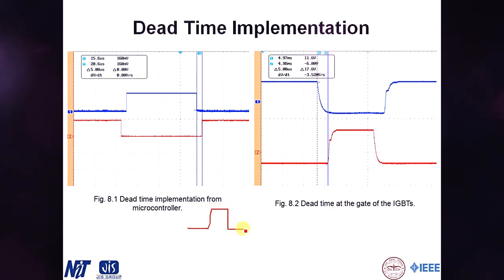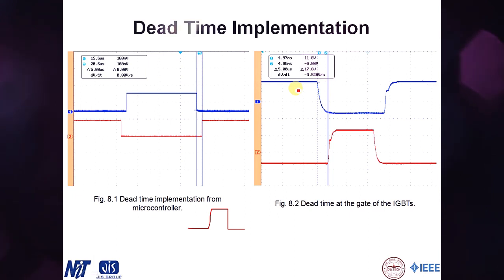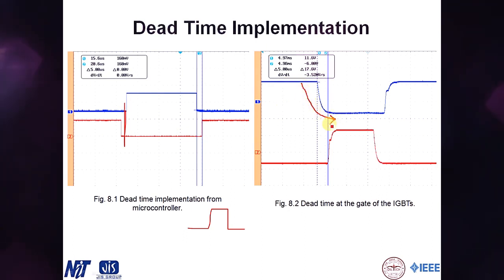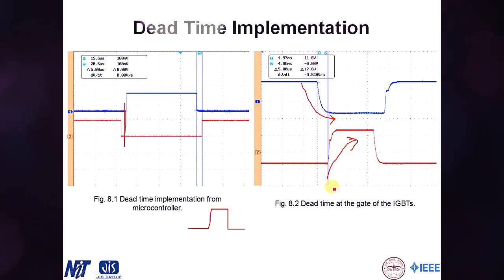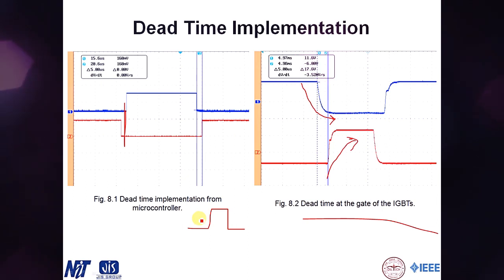This is the dead time implementation. Since IGBTs do not switch ideally, the upper and lower IGBTs in a limb need dead time between turn-off and the other's turn-on. A five-microsecond dead time delay has been provided — it takes five microseconds to turn off, and that time is used for switching on the other IGBT in the same limb.